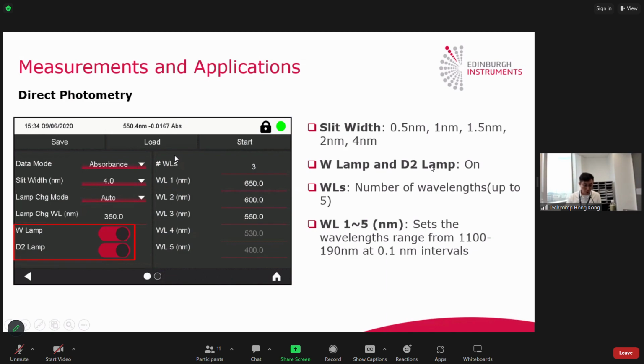Apart from the data mode, you can also change the slit width from 0.5 nanometers to 4 nanometers. And remember to check that the W lamp and also the D2 lamp are on. The status is on. And then you can select the number of wavelengths, up to 5. The screen is using 3 as the sample. And then you can set up the wavelength from 190 nanometers to 1100 nanometers here.